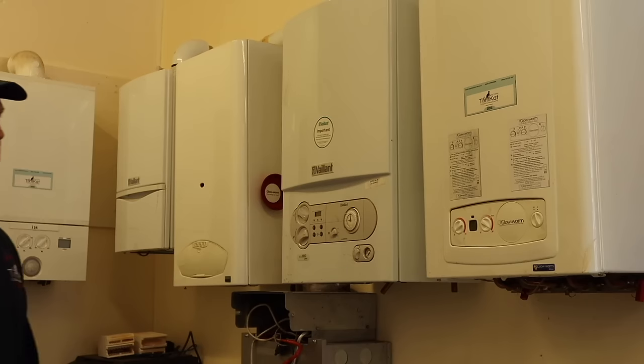So with the correct size boiler and the correct controls, a vast majority of homes in the UK could save between 10 and 25% on their fuel bill over the year. It's not just getting the correct boiler and the correct controls, it's also teaching the customers how to use their controls effectively. That's the biggest problem we have as engineers: getting the customer to use their boiler and controls in the correct manner they're supposed to be used.